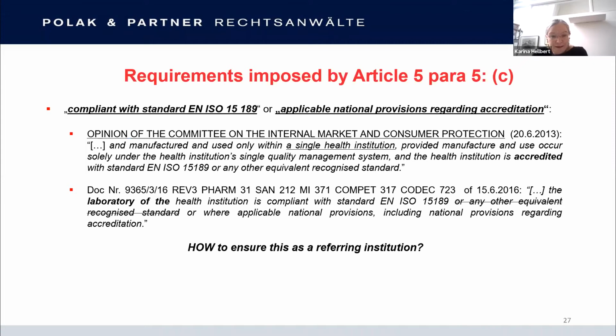So a compromise was found, and it reads: the laboratory of the health institution is compliant with standard EN ISO 15189. So it's only compliant, not accredited, or, where applicable, national provisions, including national provisions regarding accreditation. This means if the member states foresee that you must be accredited, then you have to be accredited according to the standard to make a home brew according to the IVDR. If the member states do not foresee a certain accreditation standard, then you have to be compliant.